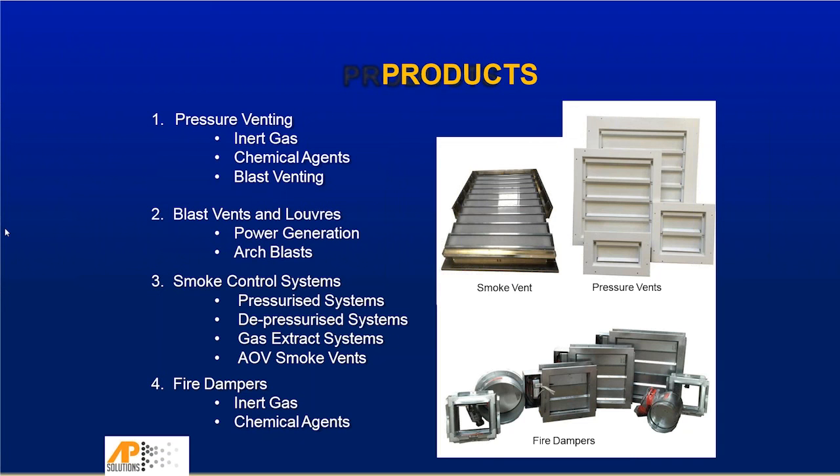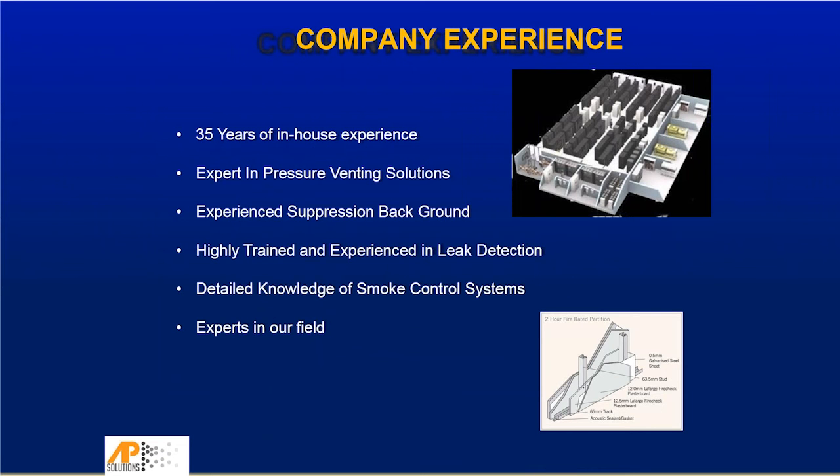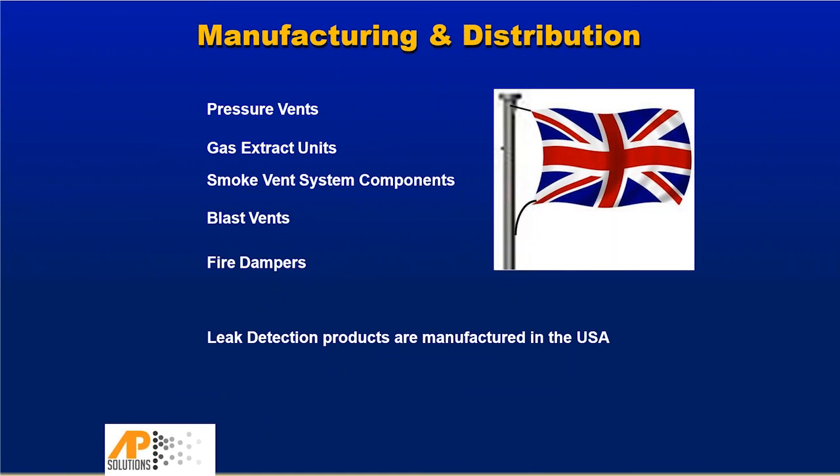Some of the key areas is fire ratings. We have UL fire rating for 2 hours, and we have European fire testing up to 4 hours on our products, and we have quite a wide range of sizes. We've moved over in recent years to a solid welded construction. We found with some pressure vents, especially two-way pressure vents, where the tolerances between the blades and the casings are very small to keep leakage to a minimum, if there's any movement in that casing, or it's pushed into a hole that hasn't been cut correctly, or it's dropped, it could get blades that stick. With our solid welded construction, that no longer occurs. And for installation purposes, once the hole is cut, it's about a 15 to 30 minute install. And we provide wall sleeves to fill in the gaps if you have a cavity wall or openings within that wall.